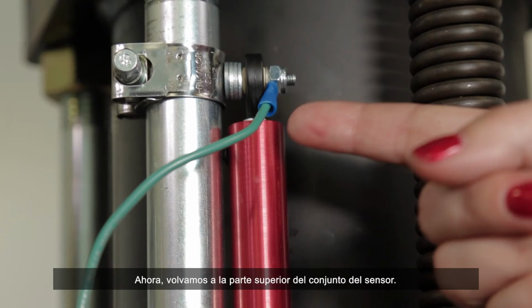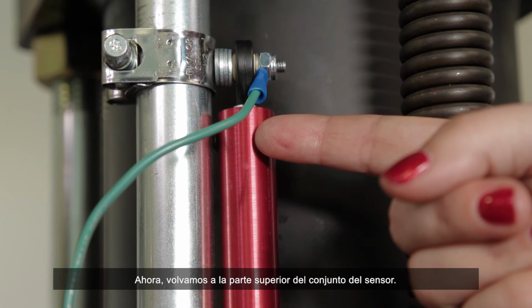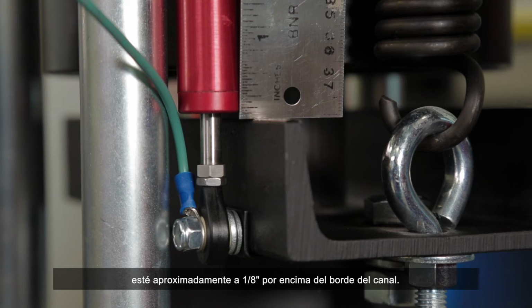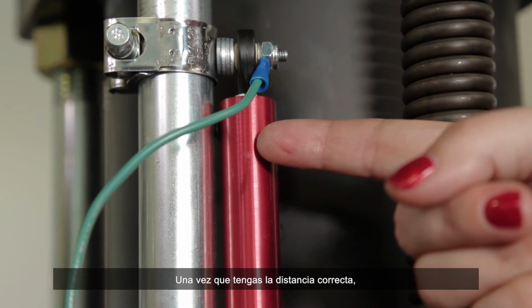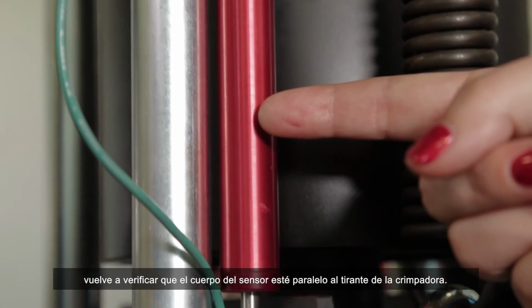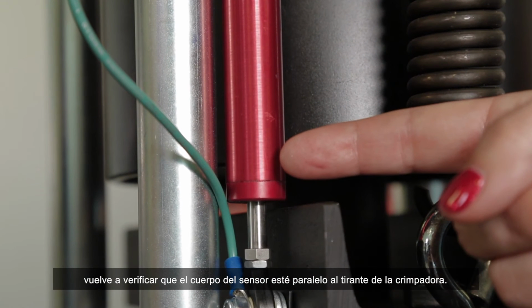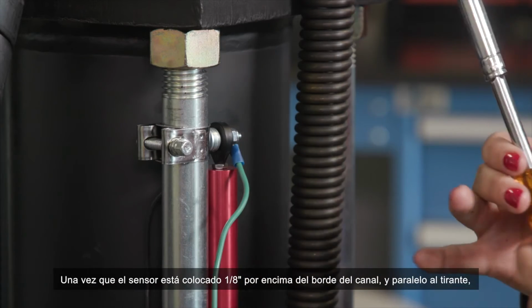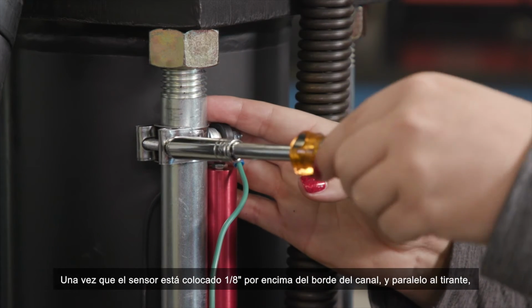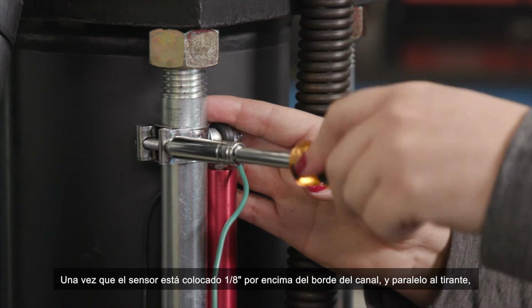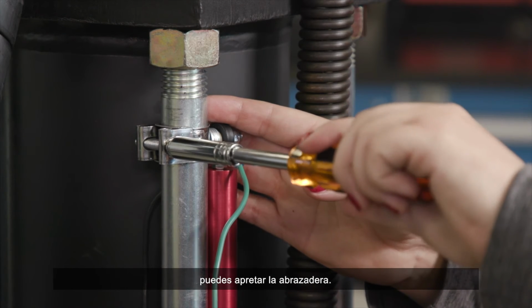Now let's move back to the top of the sensor assembly. Move the hose clamp so that the body of the sensor is approximately 1/8 of an inch above the lip of the channel. This must be done before finalizing the positioning and fully tightening the clamp. Once you have the distance correct, double check that the body of the sensor is parallel to the crimper tie rod. This distance and orientation is important. Once the sensor is positioned 1/8 of an inch above the lip of the channel and parallel with the tie rod, you can then tighten the clamp.